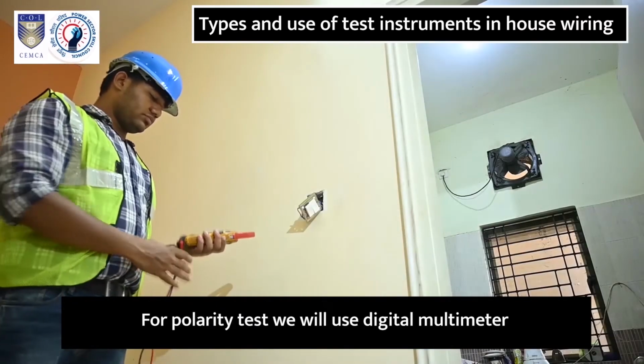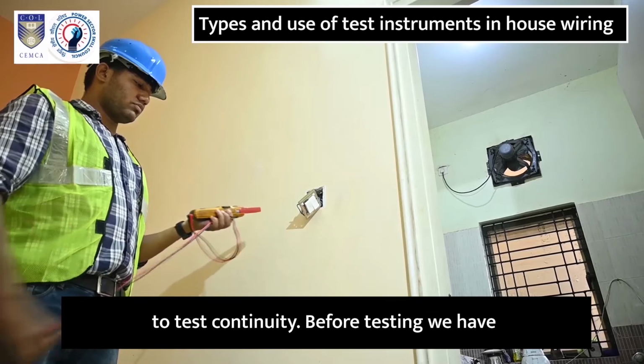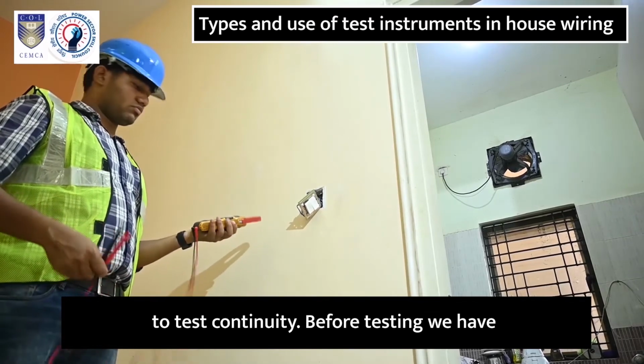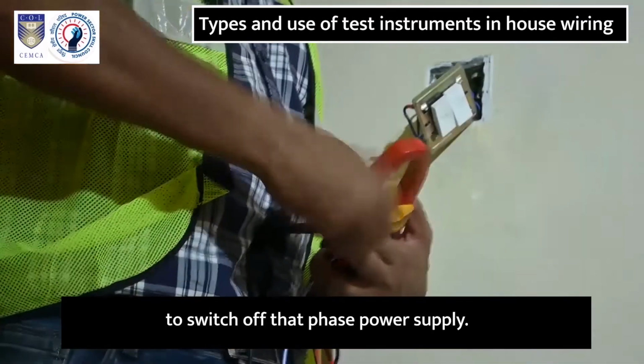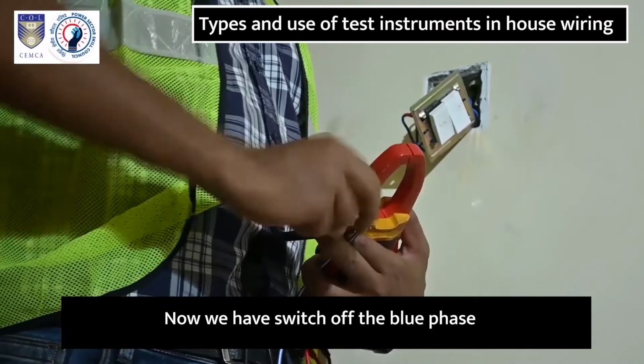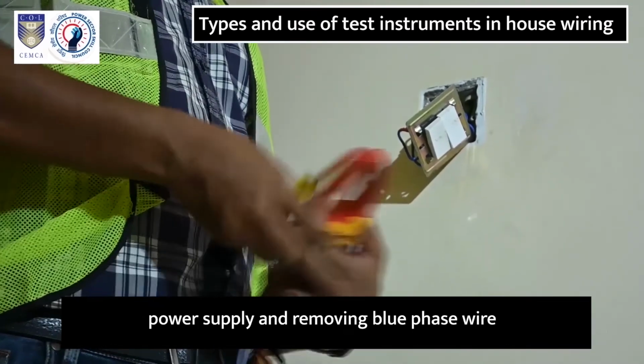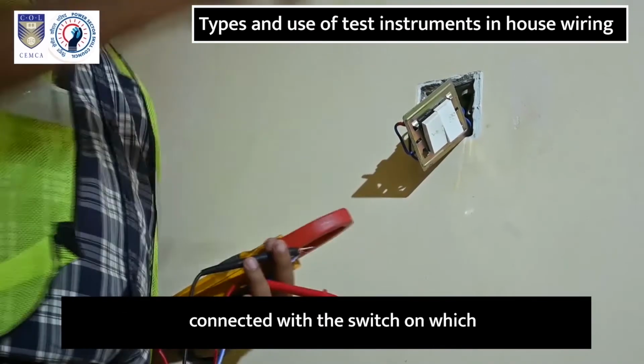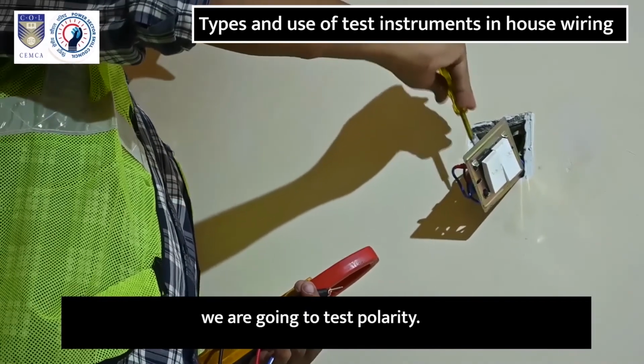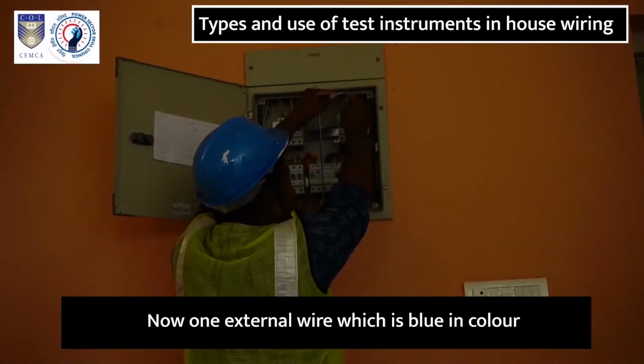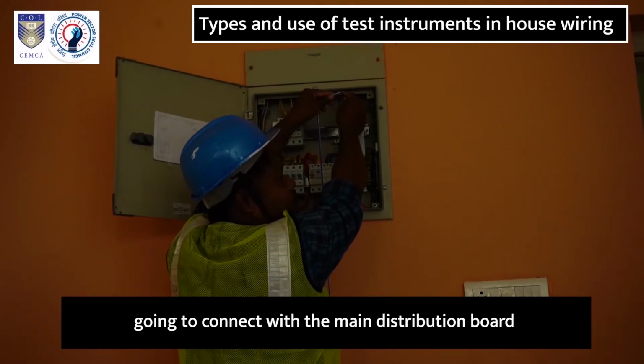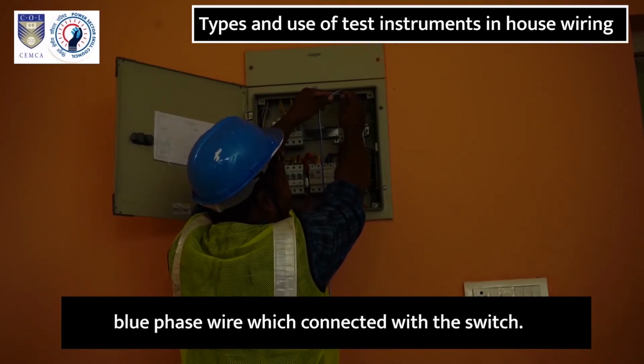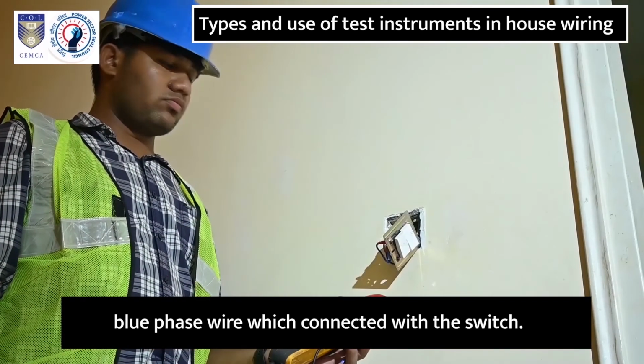For polarity test, we will use digital multimeter to test continuity. Before testing, we have to switch off that phase power supply. Now we have switched off the blue phase power supply and are removing the blue phase wire connected with the switch on which we are going to test polarity. Now one external wire which is blue in color is going to be connected with the main distribution board blue phase wire which is connected with the switch.